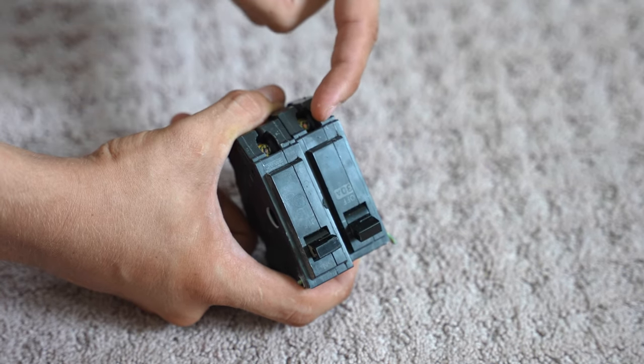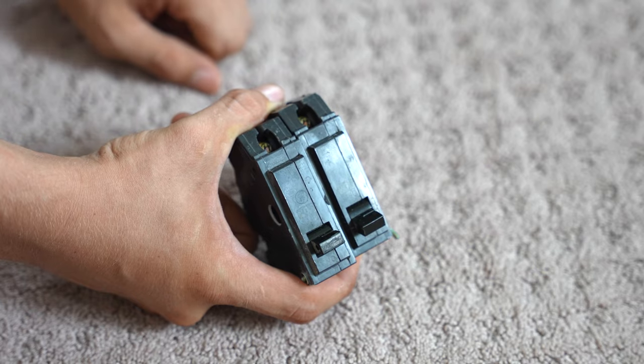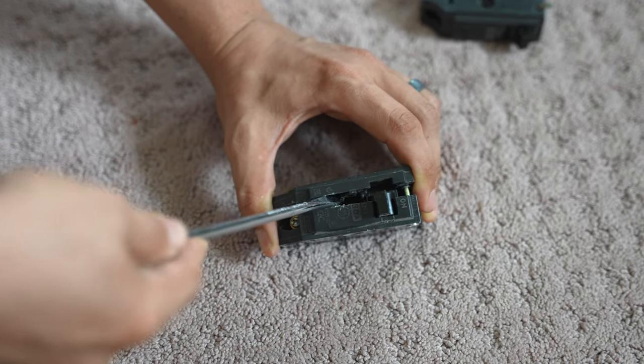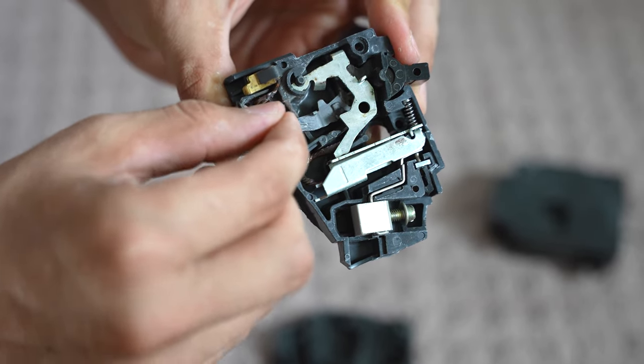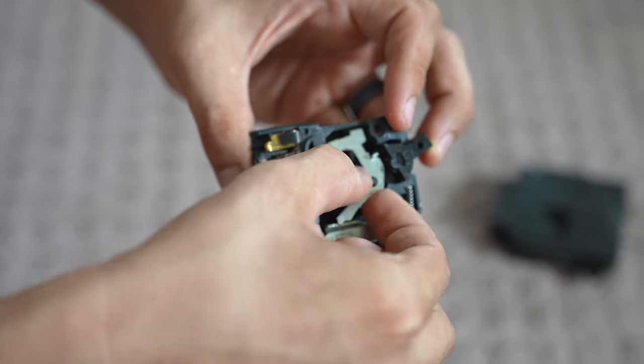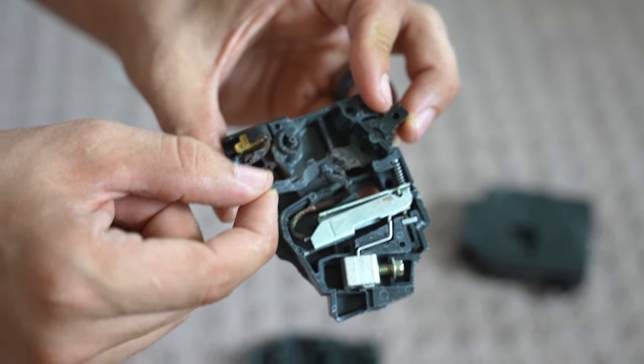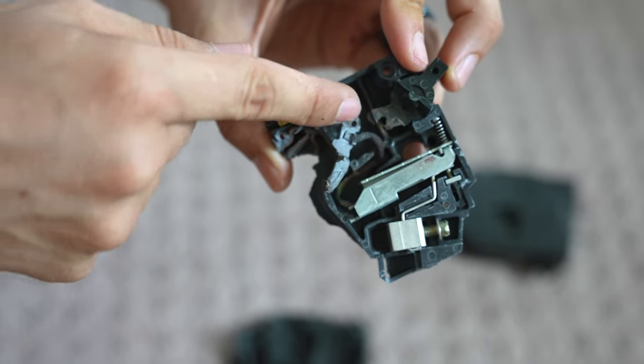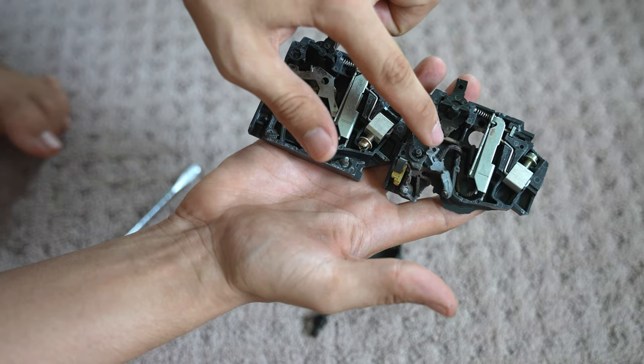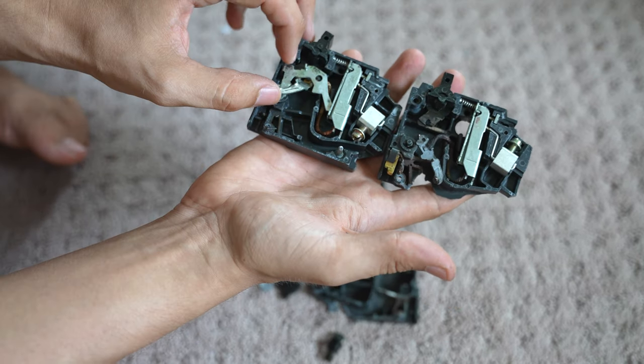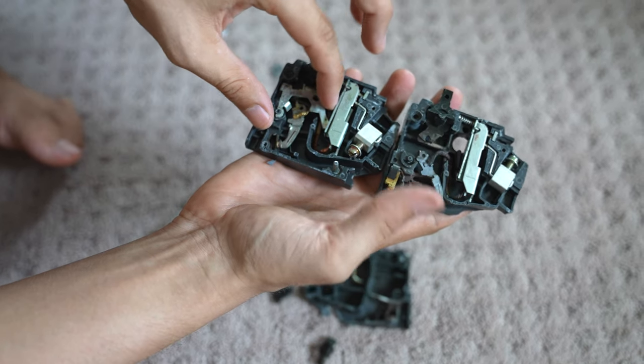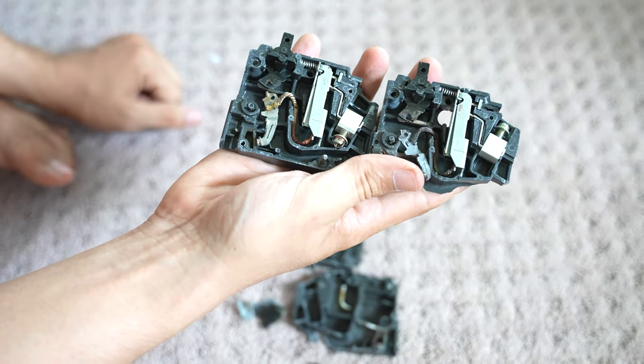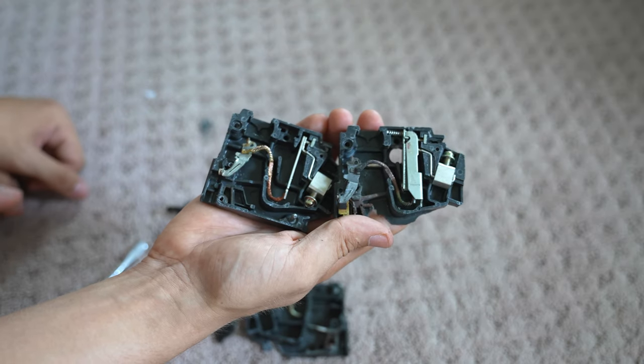So I didn't do this in the video, but technically if I checked power from here to ground, from this screw to ground, I would have had 120 volts. But this leg was broken. So when I checked both of these, I had zero. And because curious minds need to know, let's just see if we can actually see the damage inside. Okay, so from what I can tell, a piece of this plastic that held this little lever in place, the switching mechanism that goes back and forth, see how that bottom piece broke off? That was the broken part. So here we have the good side of the breaker, and here's the bad side. And you can just see the difference. This one is burnt, whereas this one is totally fine. If I take this little arm out, yeah, see how this little bracket right here is in place? Whereas this one is broken off. So that was our issue. I found this kind of interesting, so I thought I'd share it with you.